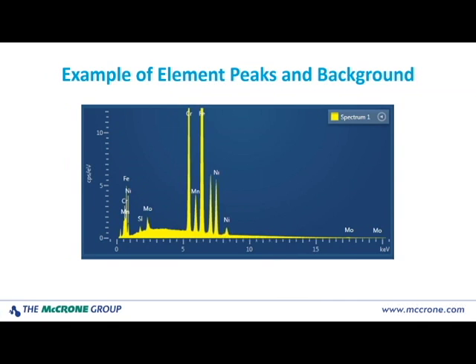Here's a quick example of an EDS spectrum. If you look at the area between about 2.5 keV where the molybdenum peak is and just over 5 keV where our chromium peak is, you can see what the background in our spectrum looks like — it tapers off to either side. Anything below our peaks is background and it gets subtracted out in the calculations. The peaks are representative of the elements in our sample, and the peak intensities are dependent upon the concentration for each element. You can have multiple peaks for chromium, manganese, iron, and nickel because these X-rays are coming from different shells or subshells. For the two nickel peaks around 7 and 8.5 keV, the first nickel peak is called K-Alpha and the second is called K-Beta. Those X-rays were generated in the K-shell; the electron that filled the void came from one orbital away to form the K-Alpha, and two orbitals away to form the K-Beta. There are also nickel L X-ray lines down at the far left.